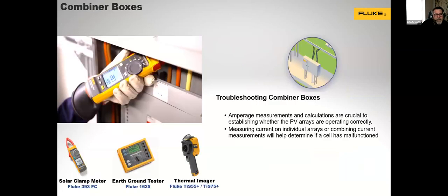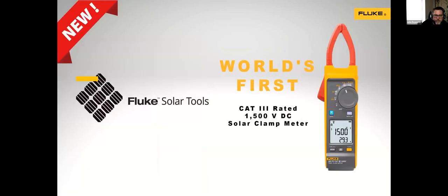Now, when we're moving on to things like combiner boxes, some of the products that you might be looking at are, again, our trusty solar clamp meter, earth ground tester, and again, thermal imager. Wherever we have cables that are carrying current, a thermal imager is always going to be useful. So we're going to be measuring amperage and taking the calculations with the clamp meter, checking earth situation, and again checking for heat sources.